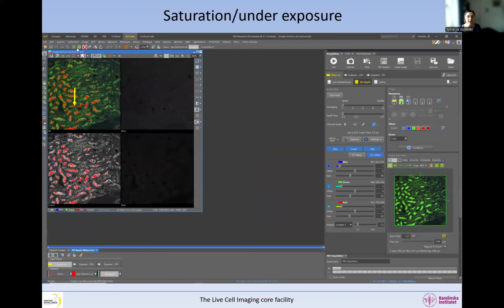However, that's not the case. If we push the saturation mask, what we can see is that channel 2, this channel, is actually saturated, and the others are not. You can do the same thing in your software. If we put our mouse somewhere in the image, we're going to see 2 things: the XY coordinate of the mouse within the image, and then 3 different numbers, each corresponding to the intensity in each of the channels. This channel is 441 at this point of the image, this one is 385, and this one is 4095. And that's a bit of a magic number.